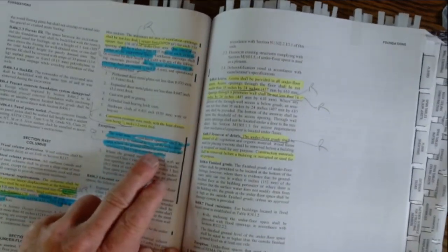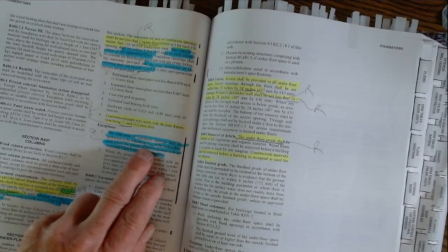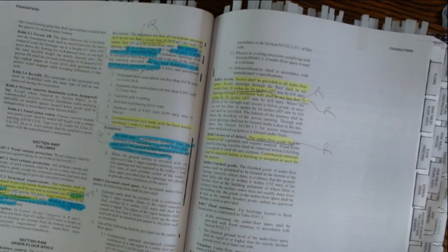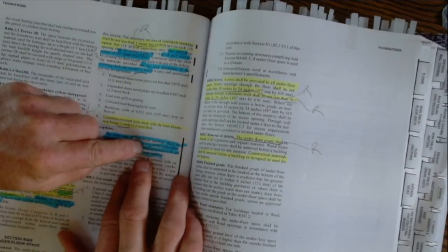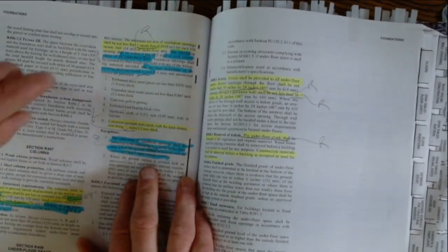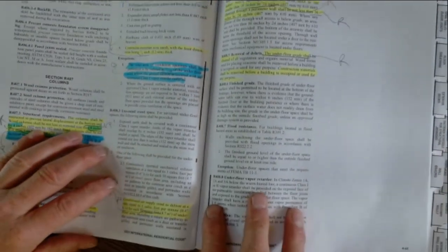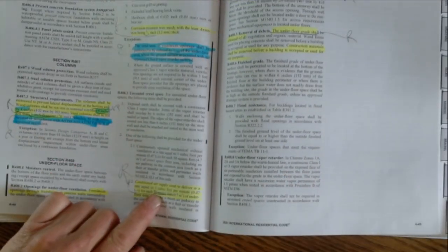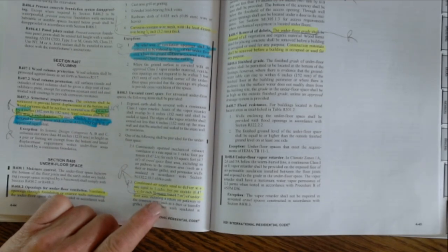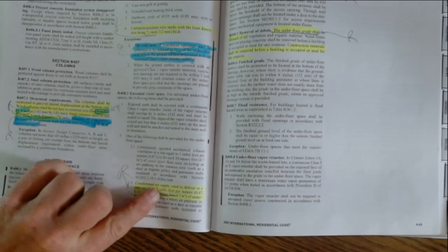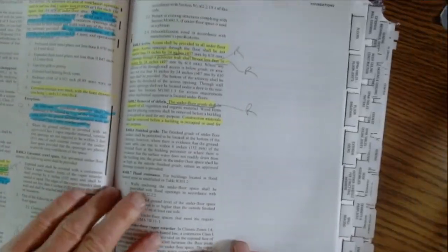Now you can reduce the foundation vents. If it's covered with a vapor retarder and it's taped and everything else, you can reduce that to 1 in 1,500. For attics, there are some allowances that reduce it to 1 in 300. You can also, for a cold area like where I'm at, where you don't want those openings, actually vent at 1 cubic foot of ventilation for every 50 square feet. It's possible too.